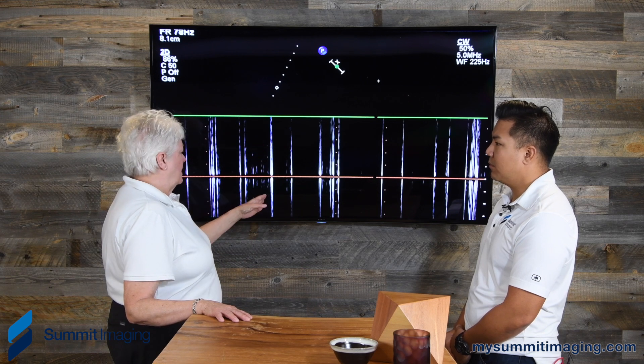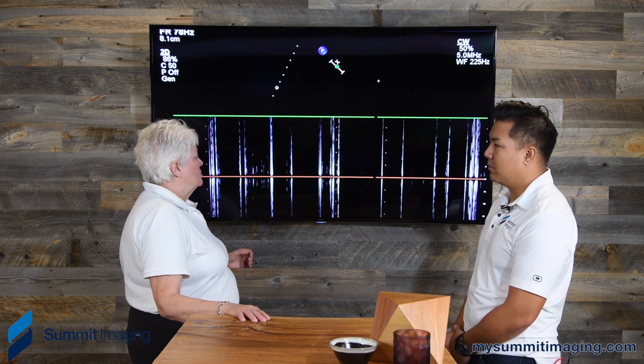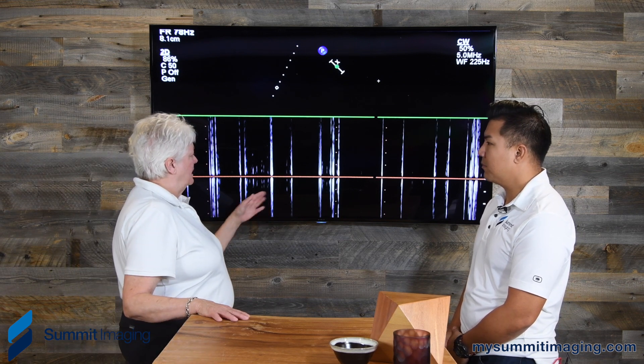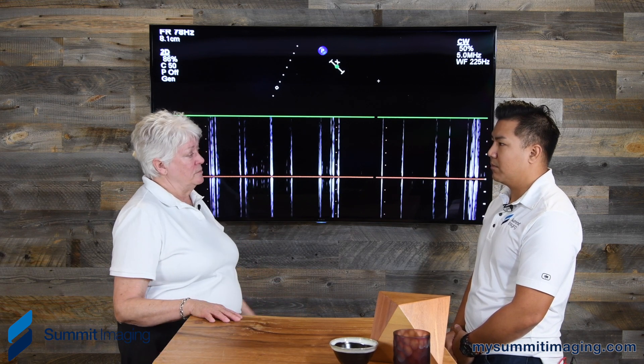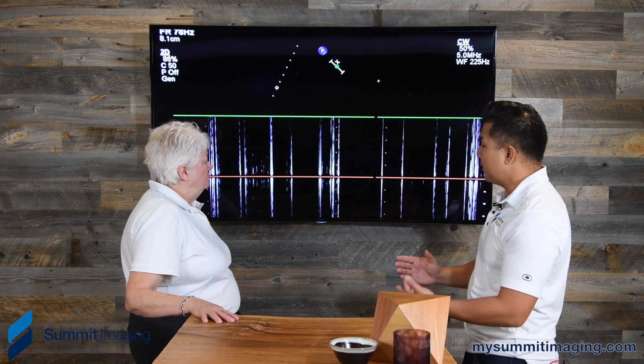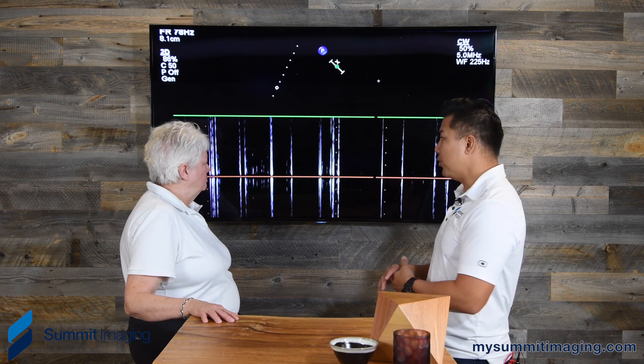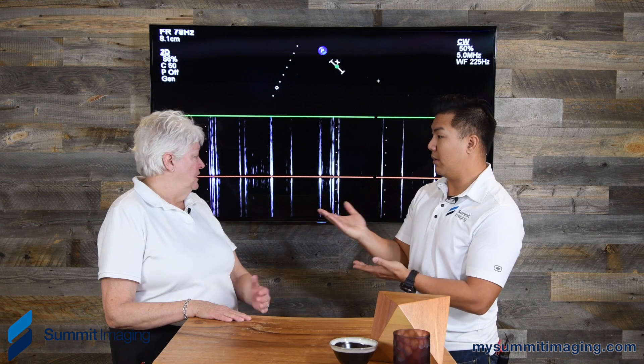Basically, you're not getting good, accurate information. How long could this go on before somebody actually sent the transducer in for repair? Who knows — it depends on how intermittent the signal is. But if this continues and gets worse, the transducer just degrades further and will compromise all of the imaging, including the 2D image. It's the kind of clinical insight from Carolyn that's so valuable, because most technicians repairing transducers probably won't realize that these spikes can actually be caused by a valve leaflet hitting the sample gate in the heart.